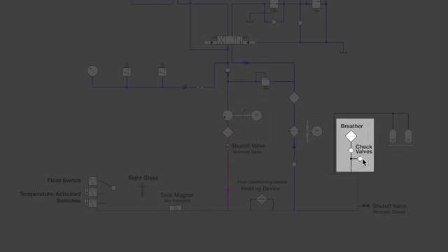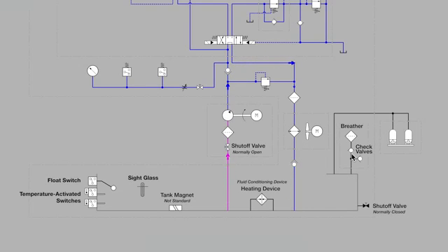And this is a vacuum breaker style of breather cap, where if the pressure inside the tank gets too high, it is vented on the check valve to the right. Or if we build up excessive vacuum in the tank, the check valve shown below the breather symbol is pulled open to draw in a volume of makeup air. But that's not the main device for exchanging air in this system.